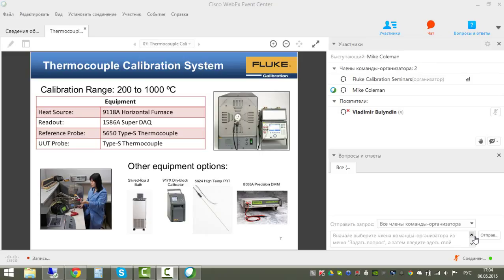The uncertainty analysis we're discussing is for a calibration system where a 9118A horizontal furnace provides heat for a comparison calibration. The readout is a Fluke 1586A Super DAQ, with a primary channel connected directly to the meter and a multiplexer box on top where additional thermocouple channels are located. The reference probe is a 5650 Type-S thermocouple calibrated by fixed-point calibration at Fluke, and the unit under test is also a Type-S thermocouple.